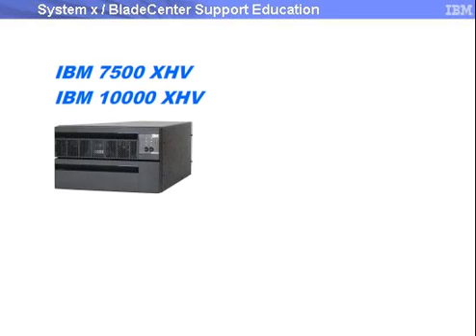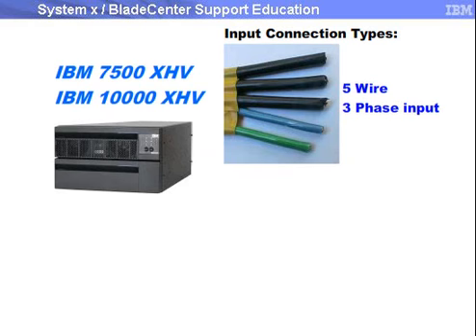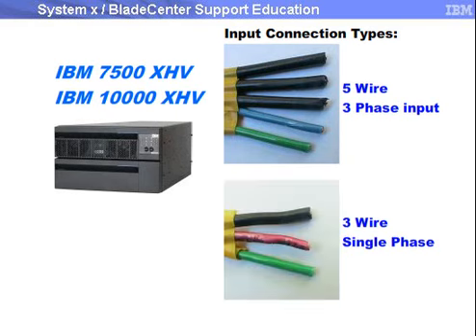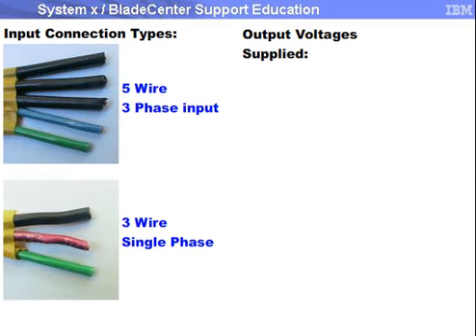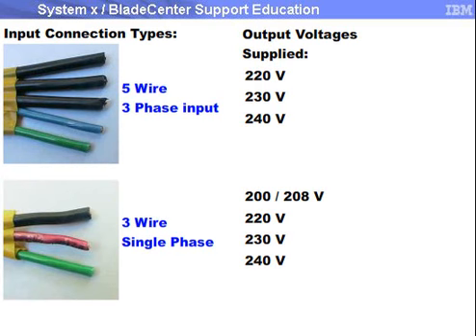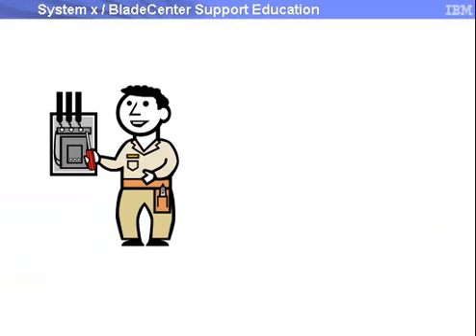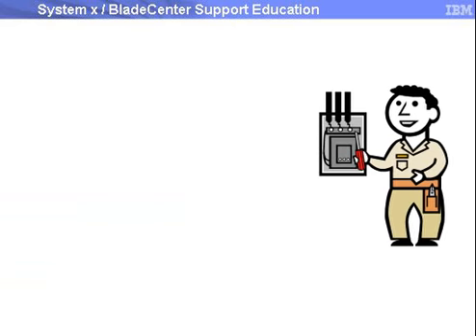The IBM 7500XHV and 10000XHV UPS power inputs are hardwire-only connections. There are two supported input wiring types: 5-wire three-phase input and 3-wire single-phase input. Connection to a three-phase input supports 220, 230, and 240 volt output operation. Connection to a single-phase input supports 200, 208 volt, or 220, 230, 240 volt output operation. All wiring must be performed by a qualified electrician.